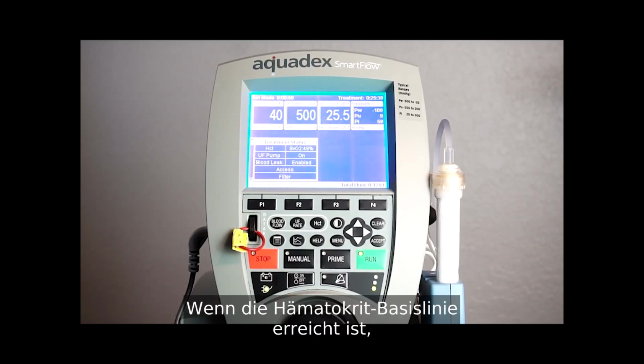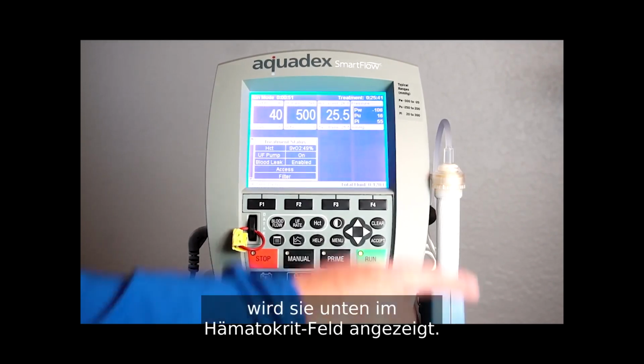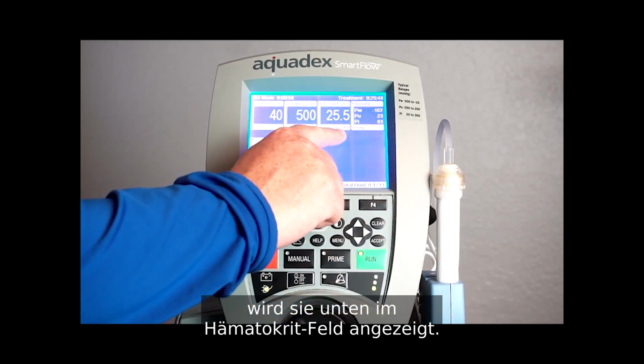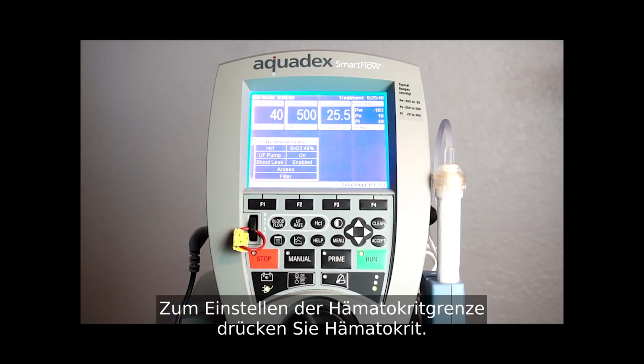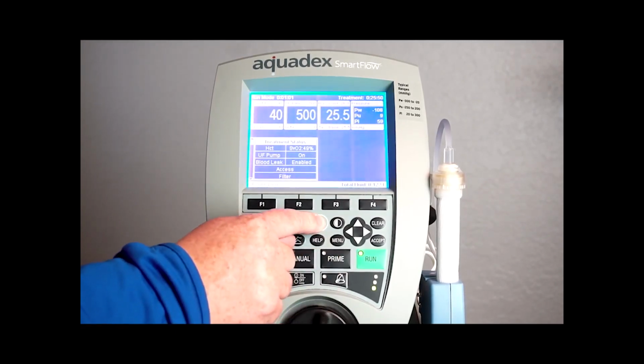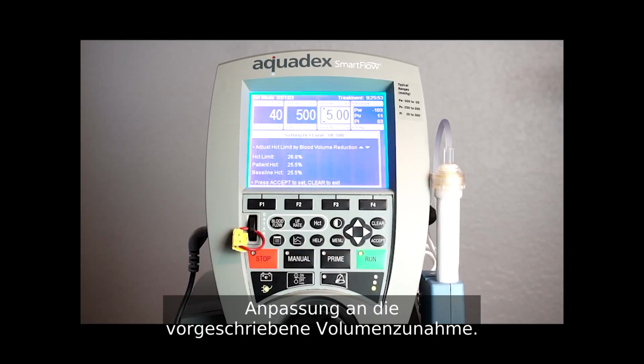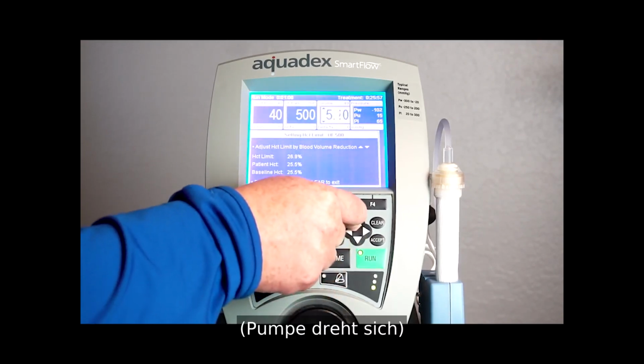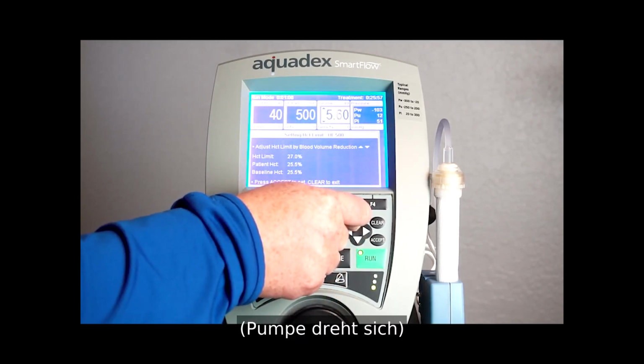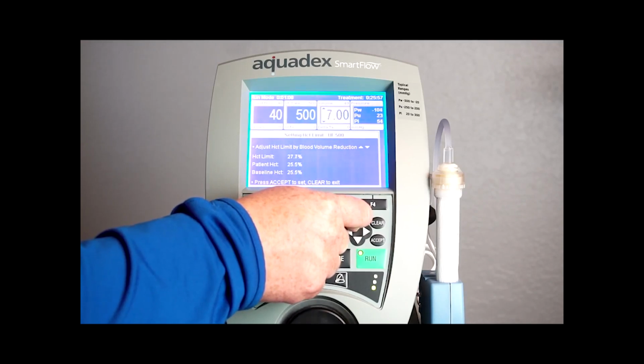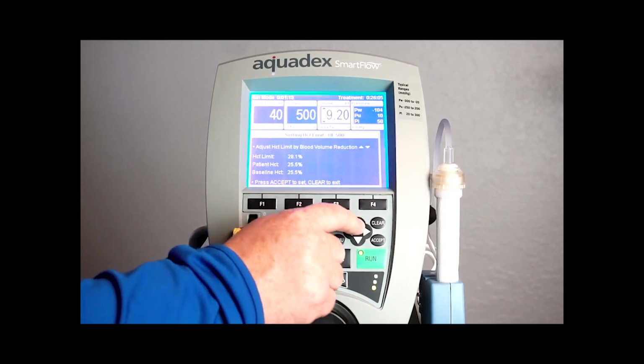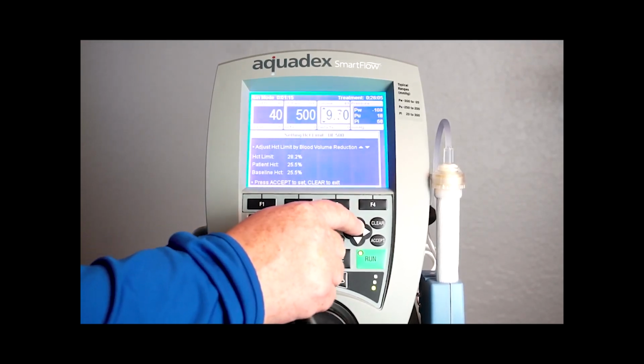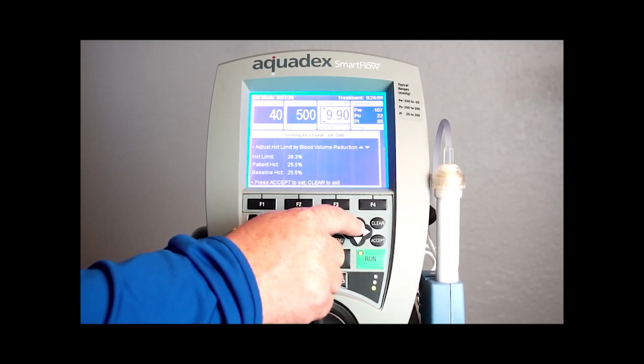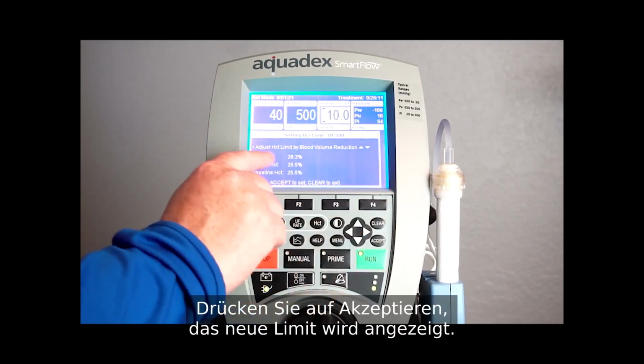When hematocrit baseline is reached, it will be displayed at the bottom of the hematocrit box. To adjust hematocrit limit, press hematocrit. Adjust to prescribed volume increase. Press accept.